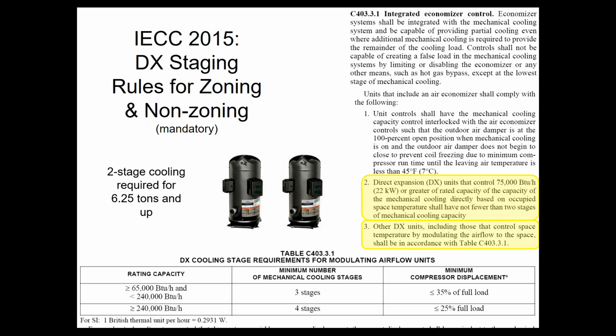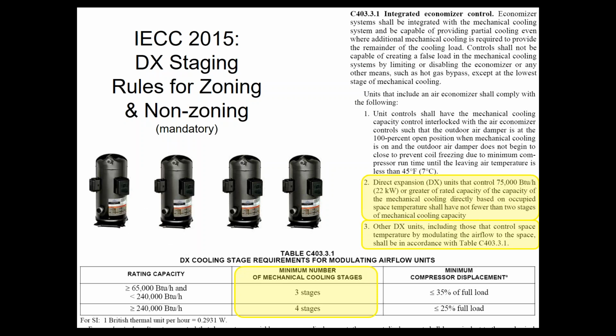Bullet number 3 is the one that gets debated a little bit. Other DX units that control space temperature by modulating airflow to the space, right? So that means if you have, once again, VAV or VVT systems where a thermostat on the wall, space temperature, is controlling the damper, airflow, then you must have either 3 or 4 stages of cooling, depending on how big your cooling system is. This one got debated quite a bit in Illinois. If you go to the Illinois frequently asked questions section on the website, you will see the interpretation that these systems need to have the 3 and 4 stages if you have the zone dampers on. Wisconsin does not have an interpretation like that yet, but most states do, so I would expect Wisconsin would follow suit.